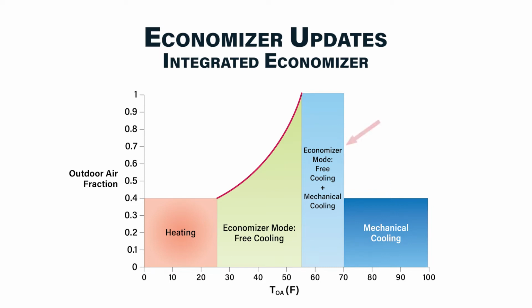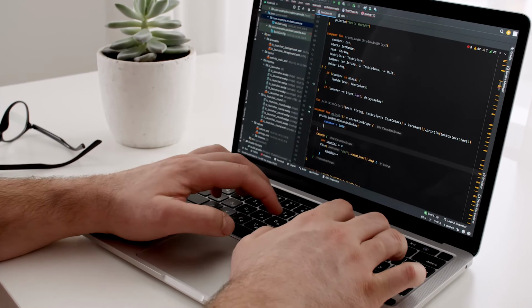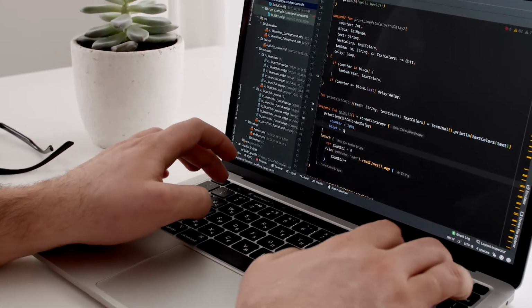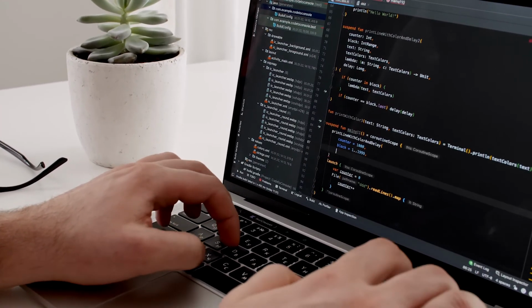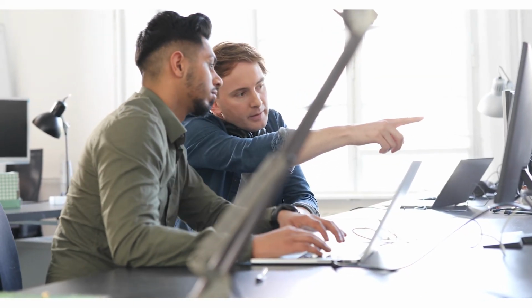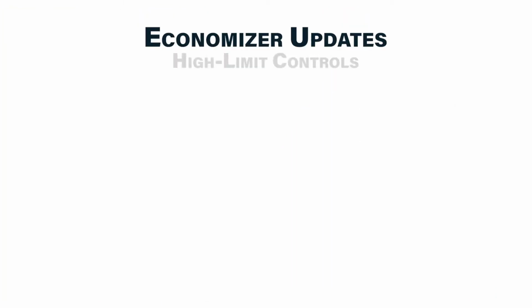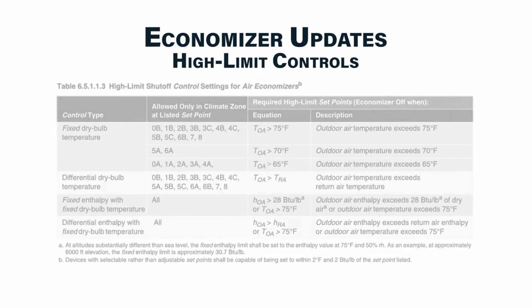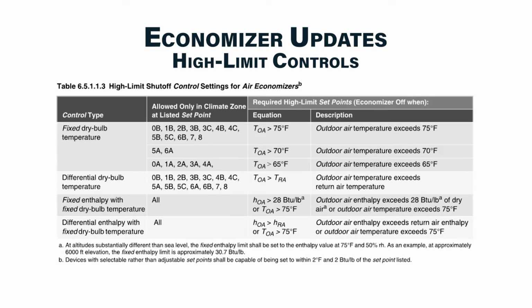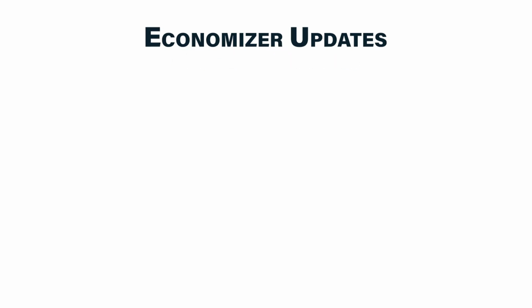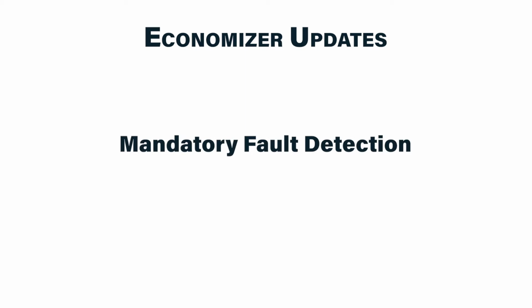But how do you know when to switch from integrated economizer mode to only mechanical cooling? Well, there's several ways you could set up the controls. You could do it based on sensors, and there's some ways you can do it that saves more energy than others. To make it easier for designers and control technicians, the IECC 2018 outlines the high limit shutoff for economizer mode, which is when you switch from 100% outside air to minimum outside air in the summer. For Nebraska, again Climate Zone 5A, the easiest one to follow is to cut off the economizer when it's 70 degrees outside.